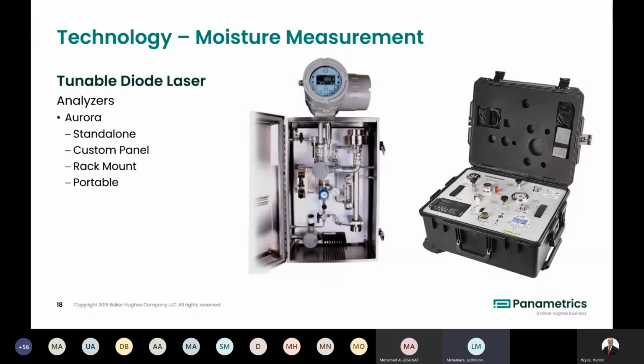So this is the analyzer itself. It's called the Aurora. The one on the left is our standalone standard configuration. It comes with a sample system. You can see the absorption chamber just on the right hand side of the sample system. In the sample system we're reducing the pressure, regulating the flow and keeping the temperature within the boundaries of measurements. We can design them in a custom panel based on a customer's requirements. We do have two other versions. We have a rack mount version for safe areas, and a portable version as well, which is the one you see on the right. That's called the Aurora Transport.